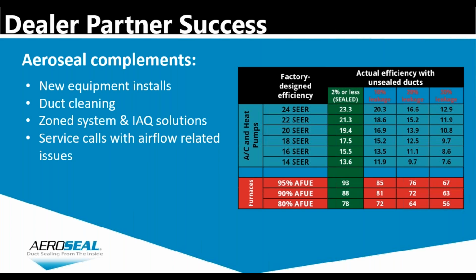So this slide here shows how Aeroseal complements these four and even more, but we'll cover these four. But with new equipment installs, I mentioned the efficiency rating. And what I hope to share here, with this chart, is the effect of duct leakage on HVAC equipment.